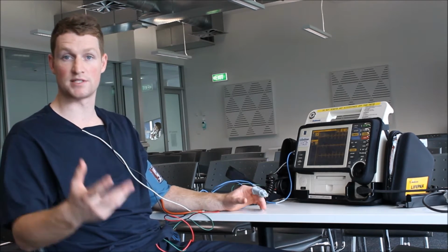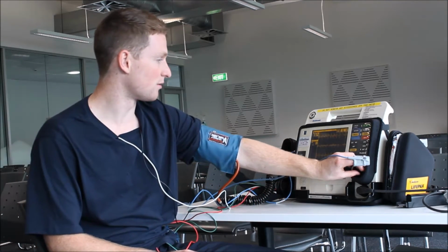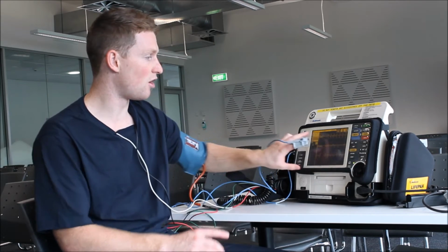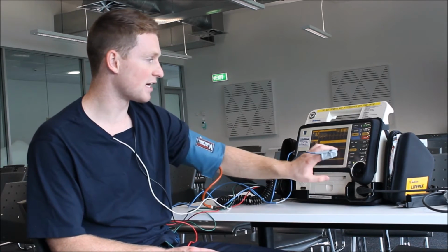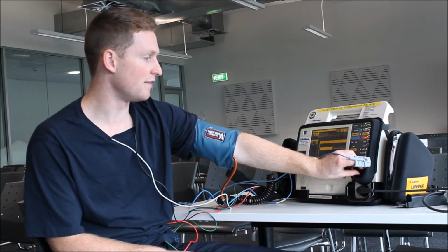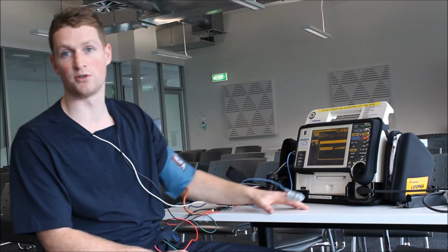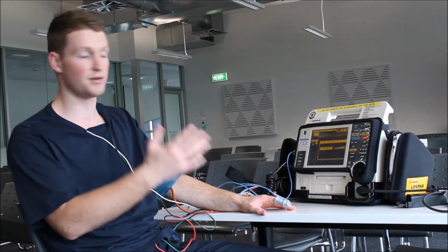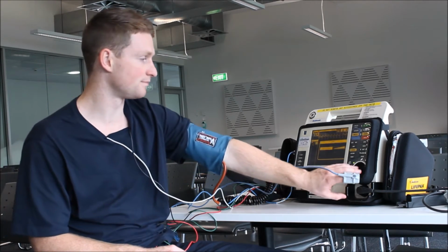Next, I'm going to adjust the QRS sound, which is part of the QRS complex in the heartbeat. I use the selector knob to hover over the heart rate in the top left hand corner, press OK, and it comes up with an option for QRS volume. Click into that and then use the selector knob to turn it up louder. This becomes quite useful for when you're in the ambulance on your own and you're trying to monitor your patient from the back. So you can use that volume there.